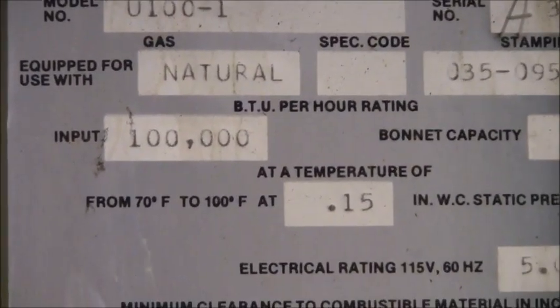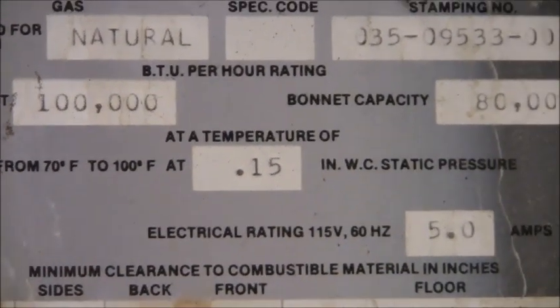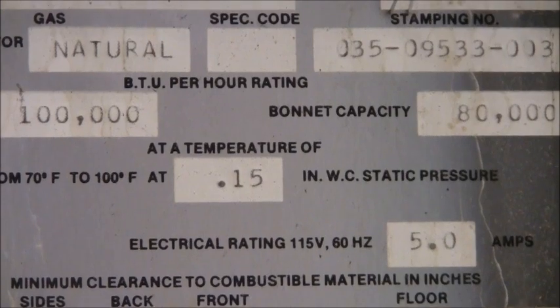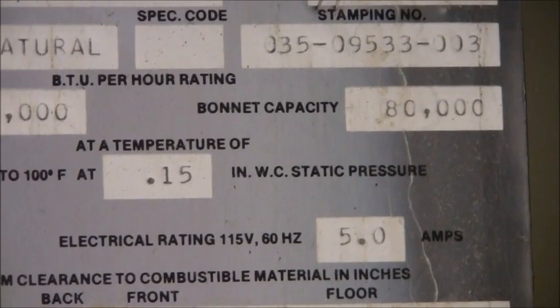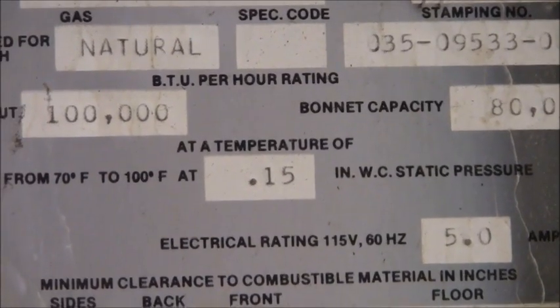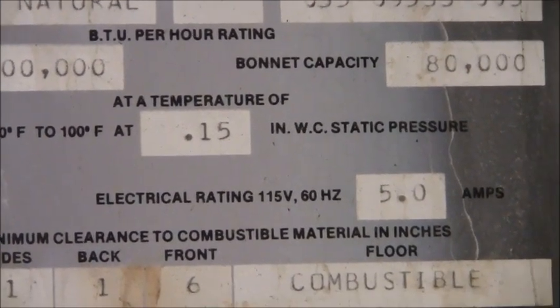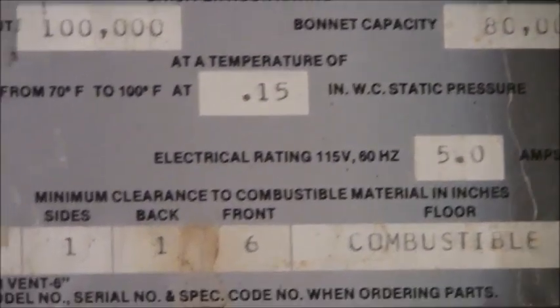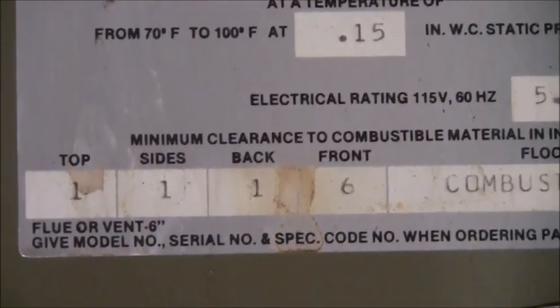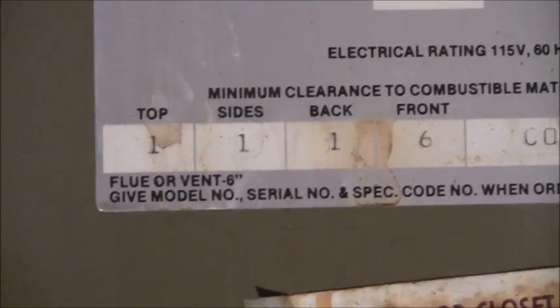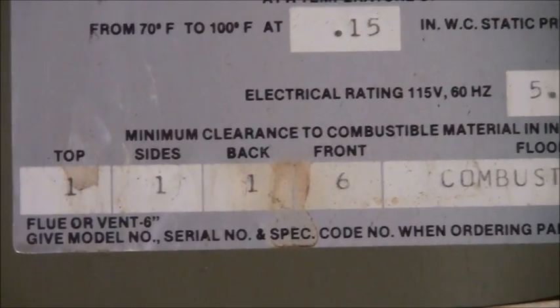It tells you that from 70 to 100 at a 0.15 inches of water column static pressure. The electrical rating is rated at 5 amps, and this gives you your clearances from combustible surfaces: 1 inch on the top, on the sides, the back, and you are allowed 6 inches in the front. So here's the front of the unit where we come to our closet door. 6 inches here. You need a minimum of 1 inch here, so you got more than 1 inch there, 1 inch here, and then 1 inch in the back.